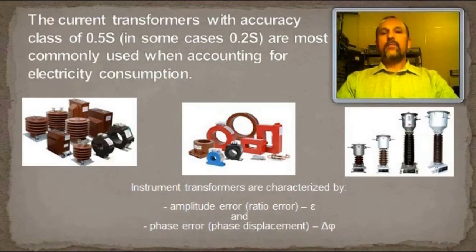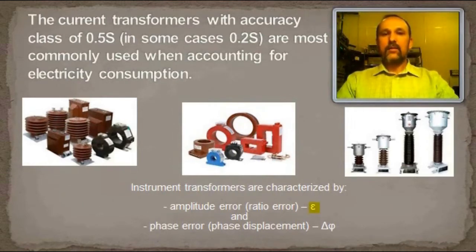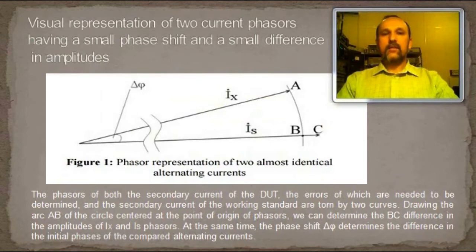When calibrating current transformer, ratio error of the device under test will be equal to the relative difference of the amplitudes of the secondary current of the working standard and the secondary current of the device under test. It is denoted by a letter epsilon. Phase displacement of the device under test will be equal to the phase difference of the set secondary currents. It is denoted as delta phi.